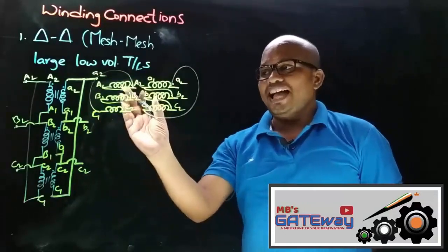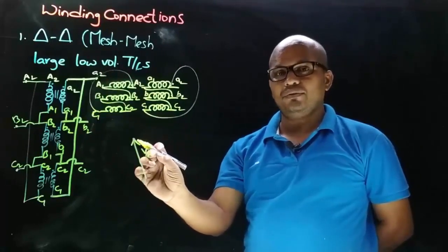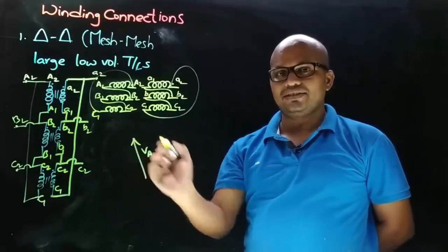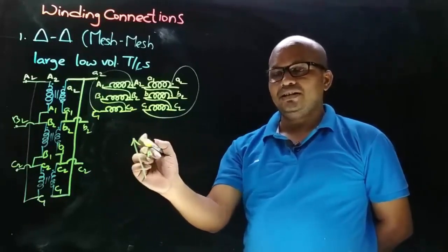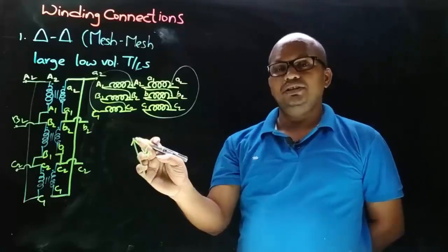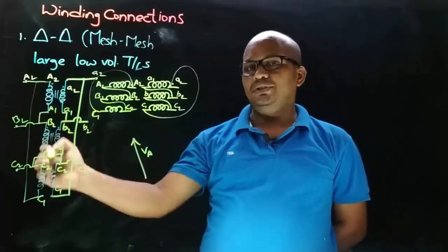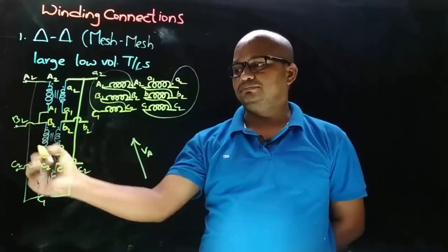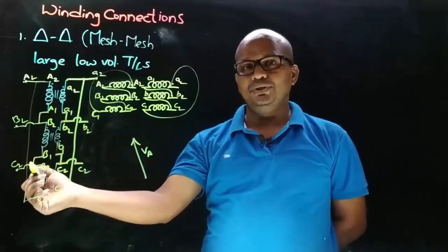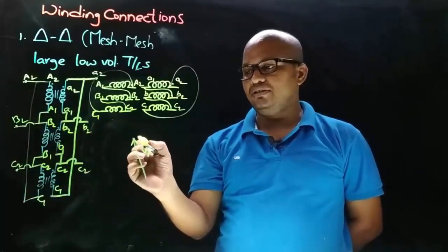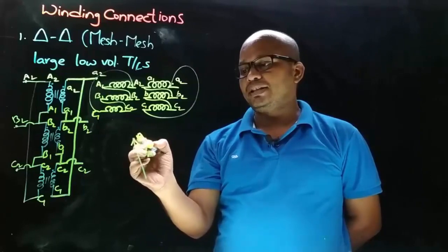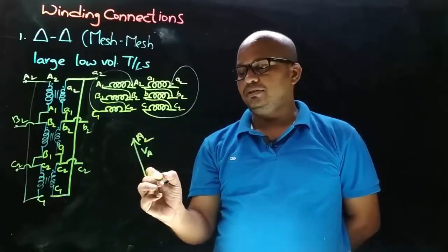Okay, now let's continue with this phasor diagram. As primary side is delta connected, and for our convenience, let's consider the primary side VA phasor like this. And here our task is to decide the terminals of this. And here arrow always points towards the connection we took from. So on primary side, we took the connections from dot ends, that is A2, B2 and C2 terminals. So as this is primary side VA phasor, this arrow will have the terminal capital A2. So this will be the capital A1.